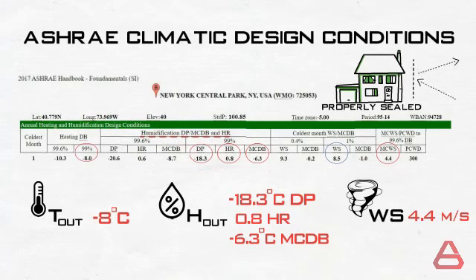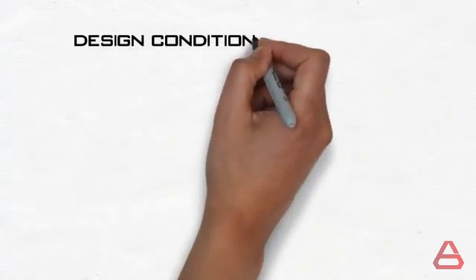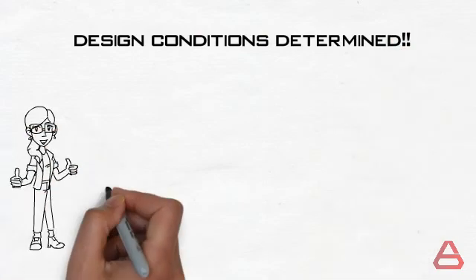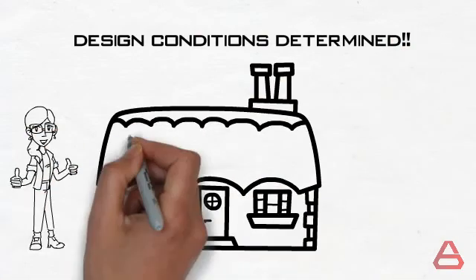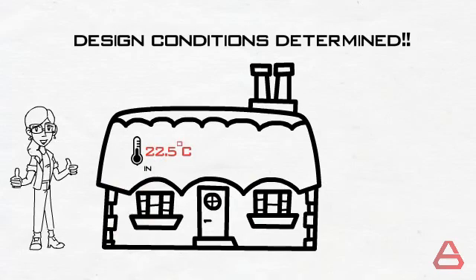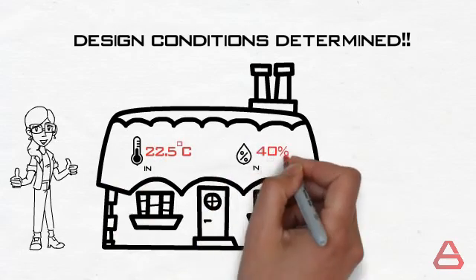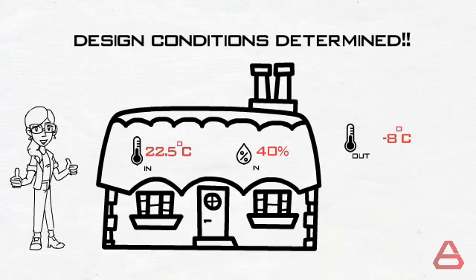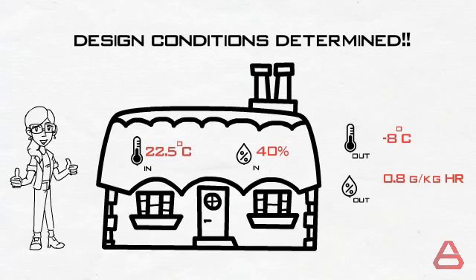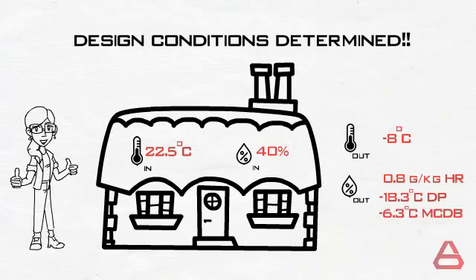And there you have it, ladies and gentlemen. The design conditions have all been determined. The indoor conditions are an indoor temperature of 22.5 degrees Celsius, and an indoor humidity of 40 percent. The outdoor conditions are an outdoor dry bulb temperature of minus 8 degrees Celsius, an outdoor humidity ratio of 0.8 grams per kilogram, a dew point of minus 18.3 degrees Celsius, and a mean coincident dry bulb of minus 6.3, a wind speed of 4.4 meters per second.